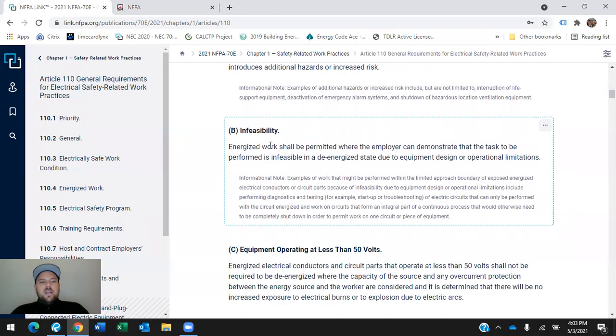B, infeasibility. Energized electrical work shall be permitted where the employer can demonstrate that the task to be performed is infeasible in a de-energized state due to equipment design or operational limitations. This is what I was talking about before. In some facilities they have live experiments going on, some running for 5 years at a time, and we cannot shut the power off. So we have to do that work hot. Again, come up with an MOP, create safe work practices, get the right environment, follow the guidelines, and work safely.